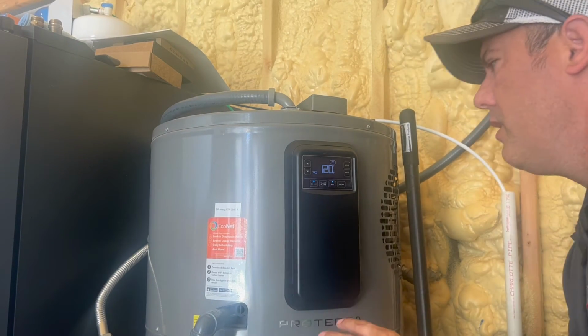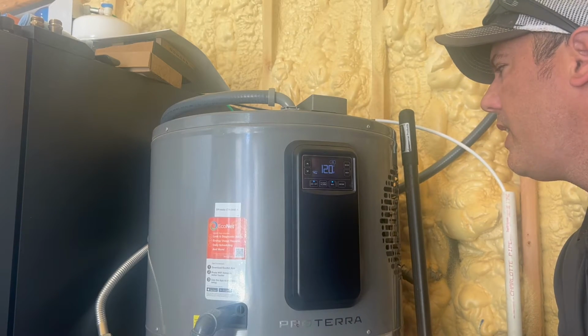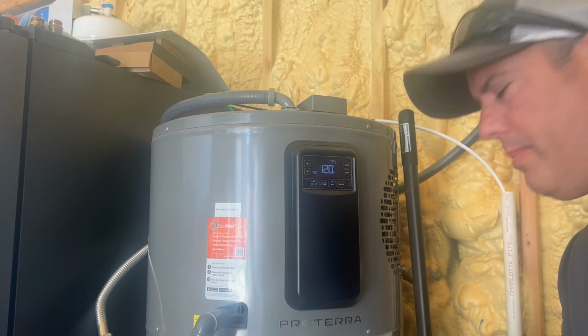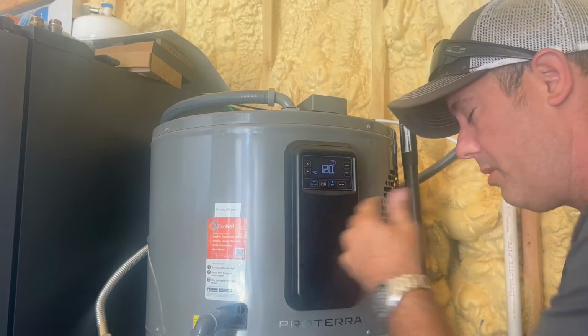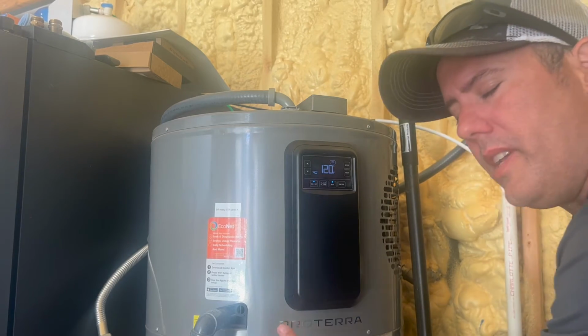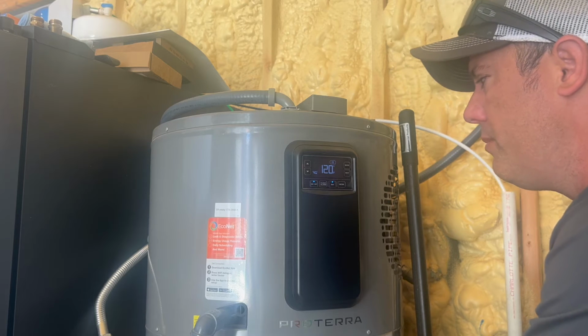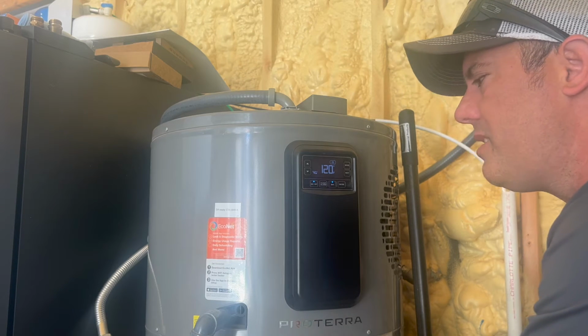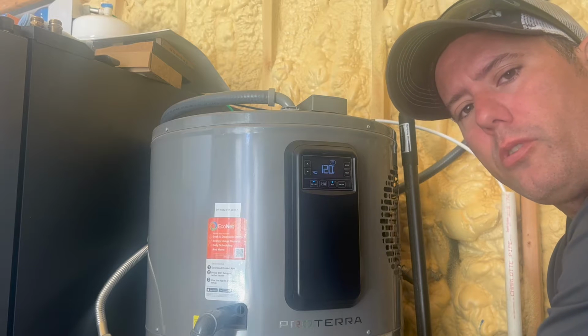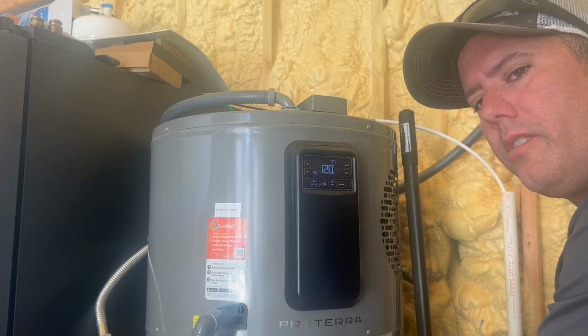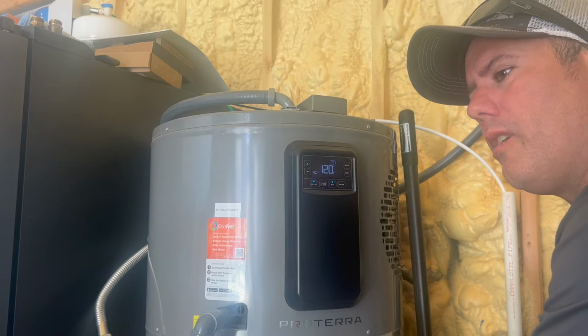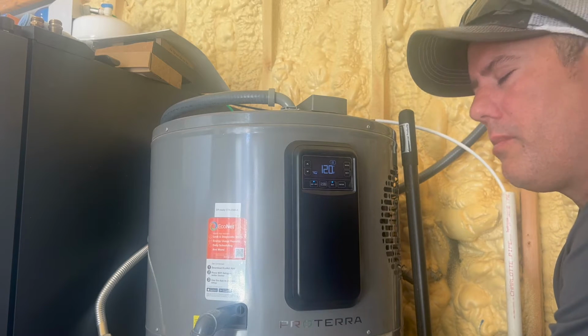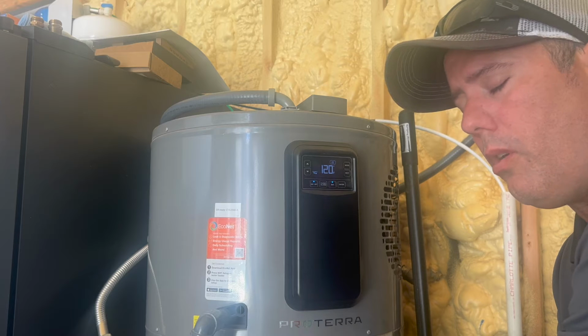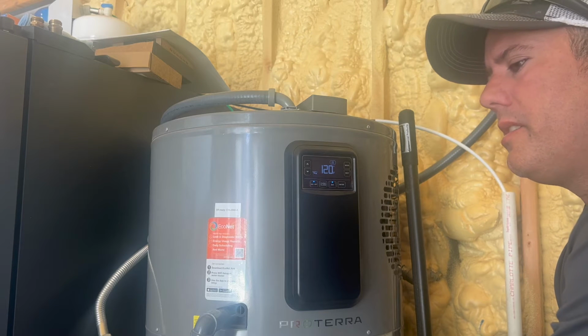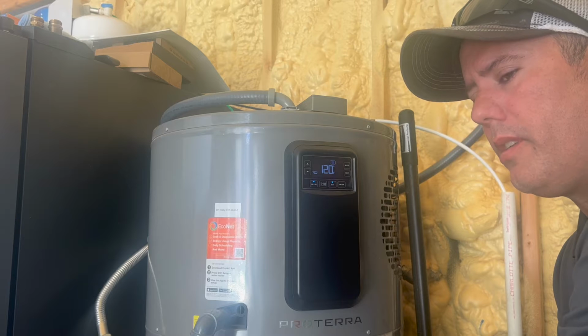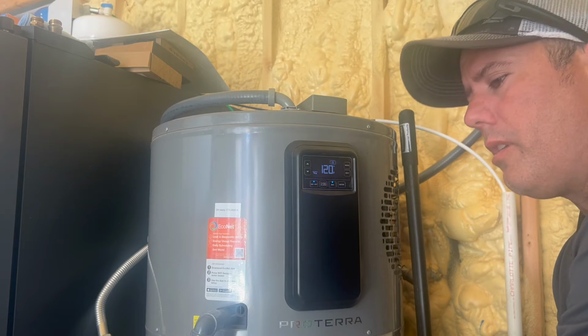Rheem Hybrid water heater. It's a Generation 5, and it utilizes a heat pump up on top and electric elements on the bottom. So we've got a heat pump on top, and what equates to basically a standard electric water heater down on the bottom. I want to review some of the easier things you can use to troubleshoot the water heater, gather a little bit of information, and then try and figure out which direction you want to go with troubleshooting if you're having some sort of a problem with the water heater, whether it be no hot water at all, or if it is a situation where you have some hot water but not enough hot water, or running out of hot water. So let's talk about that.